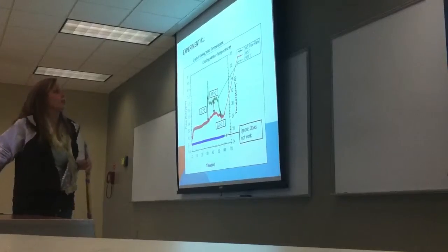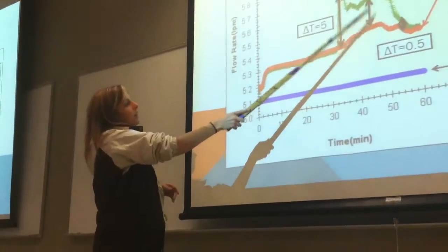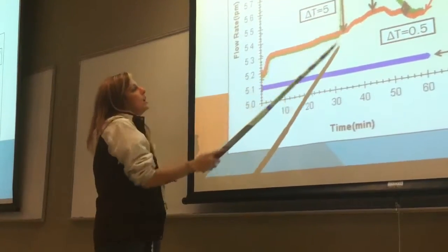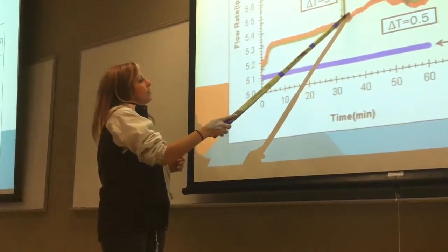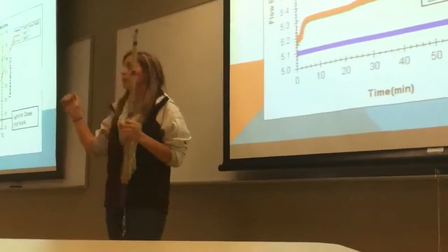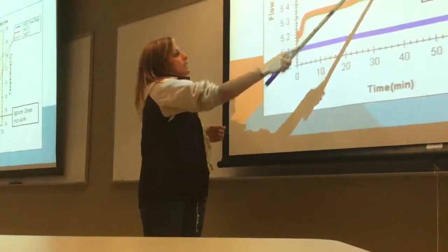And this is a graph of the cooling water temperatures. So you have your supply. Your supply is the red line, and then you have your return, which is the green line. And then these peaks should correlate with the same time that we increase and decrease the reboiler voltage. So you can see our delta T.